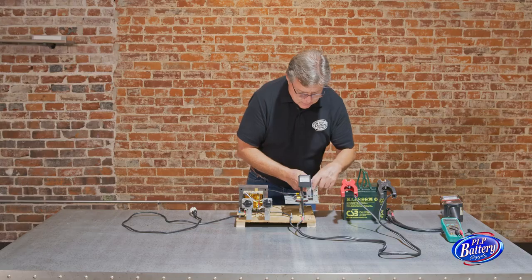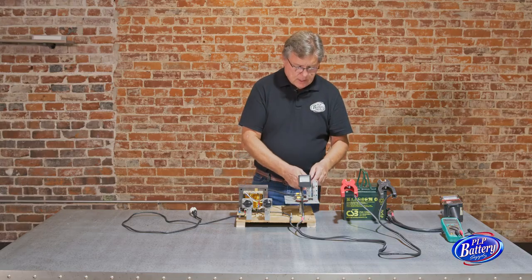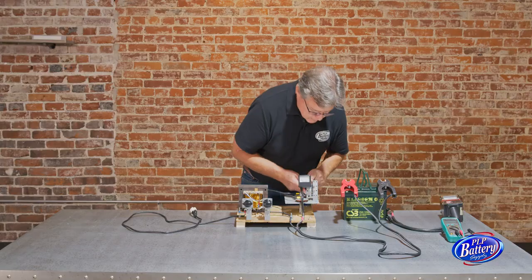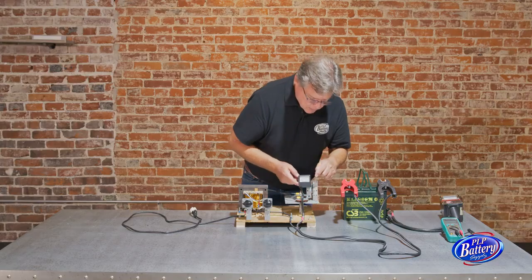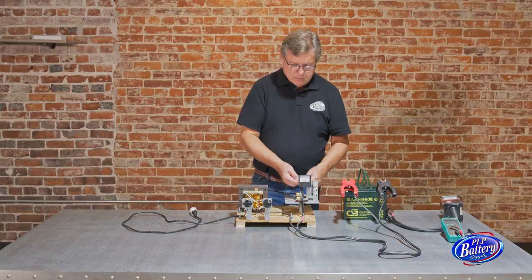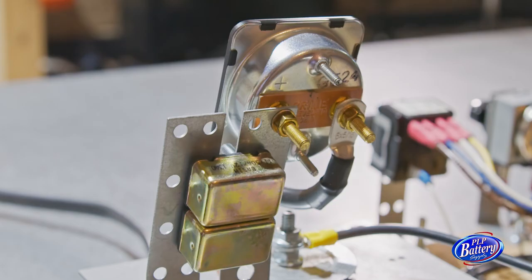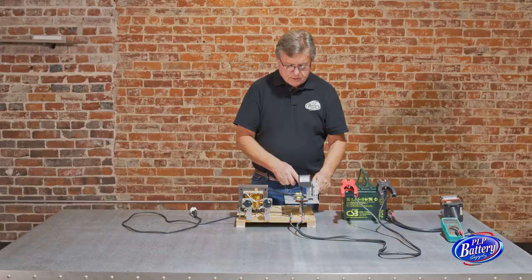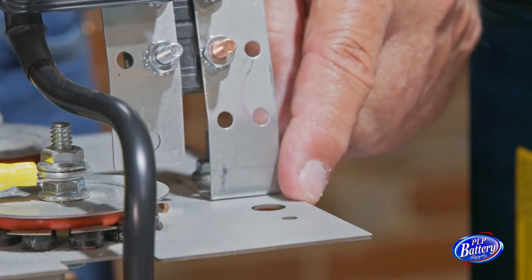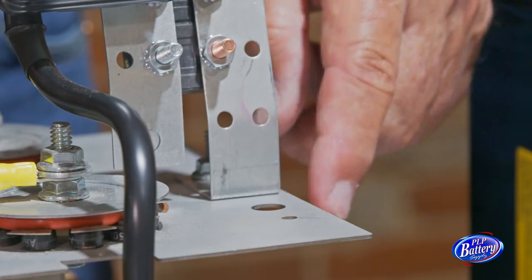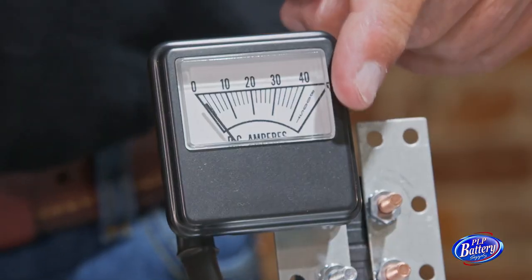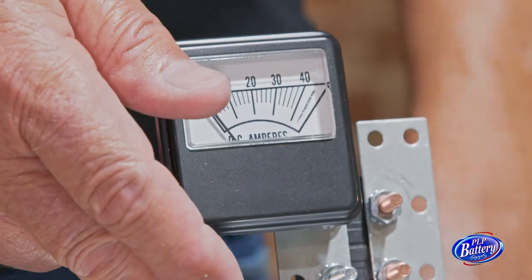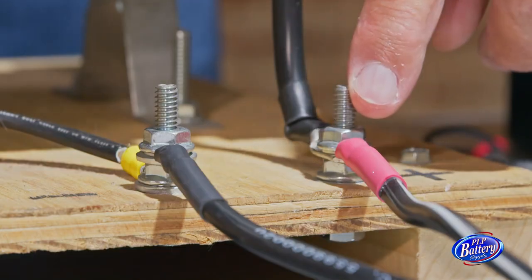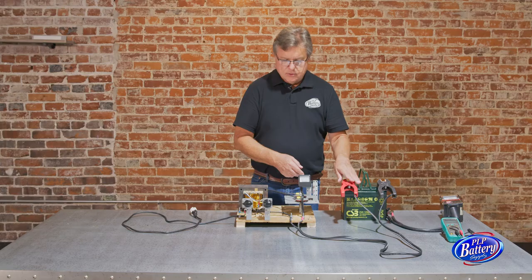That's what you're seeing right here. This is a pair of 50 amp breakers. Off of the breakers, on the other side, where we have this strap, we're connecting the meter so we can monitor how much amperage is coming out. So this is an amp meter. On the other side of the amp meter is the DC output to the positive cable. The current is actually flowing from this plate through these breakers, through the meter, because this meter has an internal bus bar. That current flows through the meter and then out the cable, out to our positive cable, to the positive clamp, and to the battery.